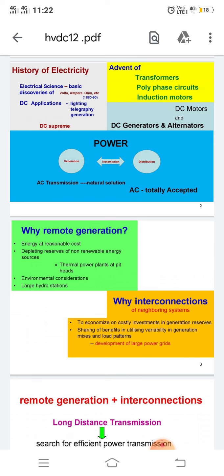The converter uses static high-power thyristors connected in series to give the required voltage rating. The same station can switch from rectifier to inverter by a simple control action, facilitating power reversal. HVDC transmission made a modest beginning in 1954 when a 100 km, 100 kV, 20 MW DC link was established between the Swedish mainland and the island of Gotland. Until the 1970s, converter stations utilized mercury arc valves; thereafter, thyristors were adopted for HVDC converters.